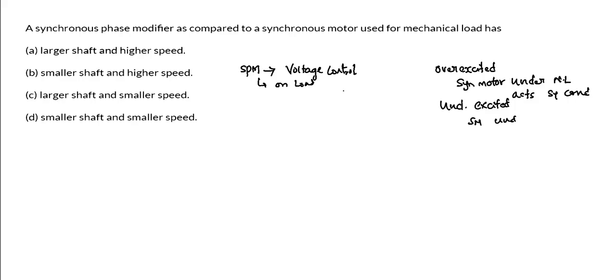So this is the synchronous phase modifier on load. The overexcited synchronous phase modifier is also overexcited, but it is under load. Okay, what is the difference between the synchronous phase modifier and the synchronous motor? The synchronous phase modifier has a smaller shaft but rotates at higher speed compared to that of a synchronous motor. So keep in mind that the synchronous phase modifier has a smaller shaft and rotates at larger speed.